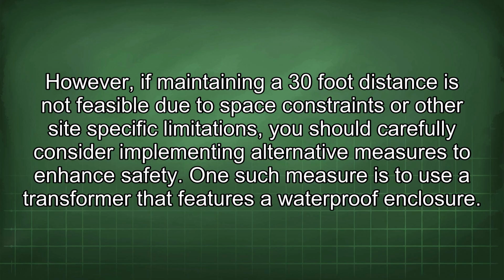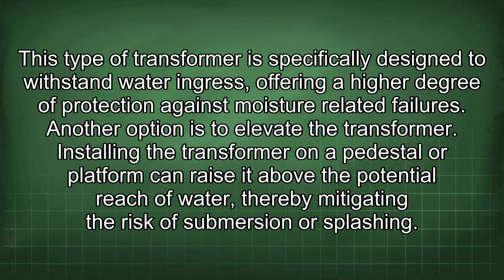However, if maintaining a 30-foot distance is not feasible due to space constraints or other site-specific limitations, you should carefully consider implementing alternative measures to enhance safety. One such measure is to use a transformer that features a waterproof enclosure. This type of transformer is specifically designed to withstand water ingress, offering a higher degree of protection against moisture-related failures. Another option is to elevate the transformer. Installing the transformer on a pedestal or platform can raise it above the potential reach of water, thereby mitigating the risk of submersion or splashing.